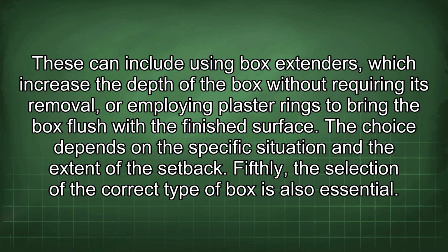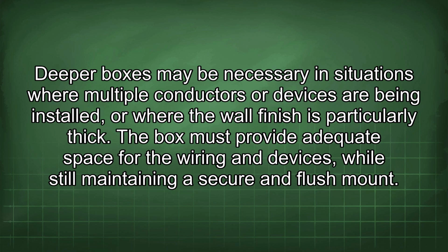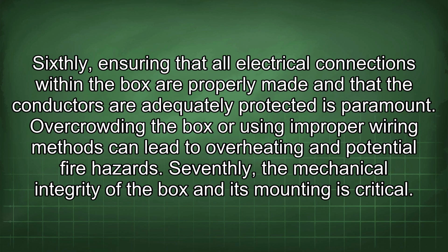Fifthly, the selection of the correct type of box is also essential. Deeper boxes may be necessary in situations where multiple conductors or devices are being installed, or where the wall finish is particularly thick. The box must provide adequate space for the wiring and devices, while still maintaining a secure and flush mount. Sixthly, ensuring that all electrical connections within the box are properly made and that the conductors are adequately protected is paramount. Overcrowding the box or using improper wiring methods can lead to overheating and potential fire hazards.